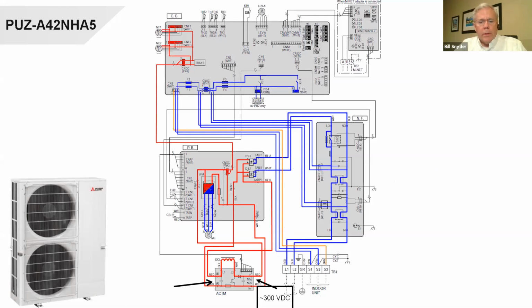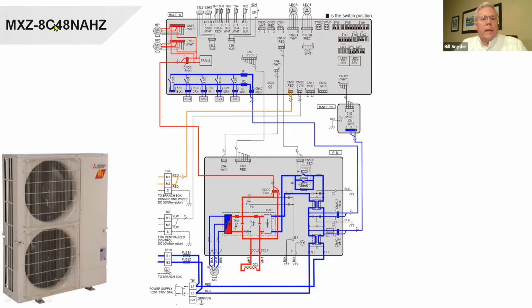And we should be looking at 300 volts DC here and here, coming in and out of that. Up here, this is an MXZ-8C48NAHZ. What that means is MXZ is a heat pump, X meaning it is a multi-zone heat pump. This can handle up to 8 zones. It is a 4-ton unit, and the HZ in the end means it's a hyperheat. So what we've got here is a hyperheat unit. This is the unit that does require a branch box.